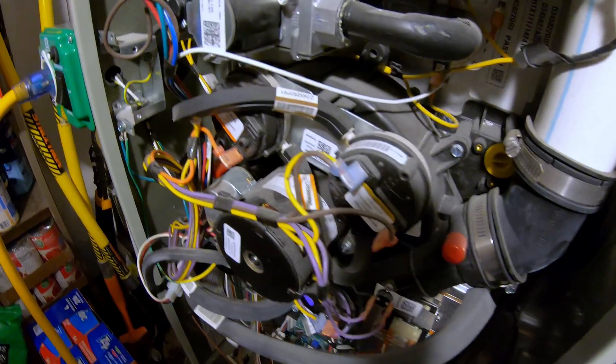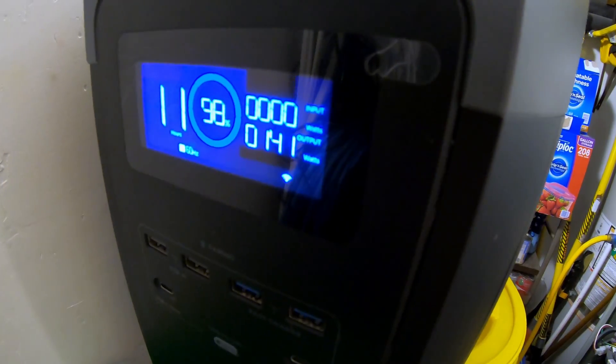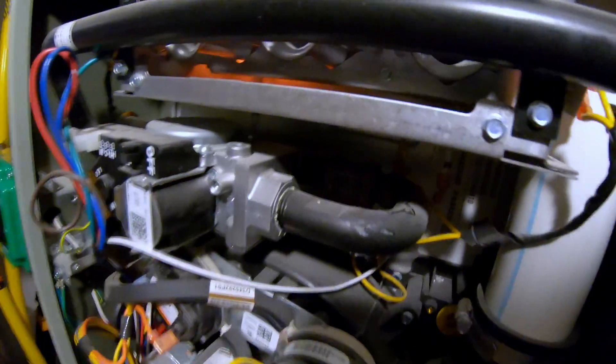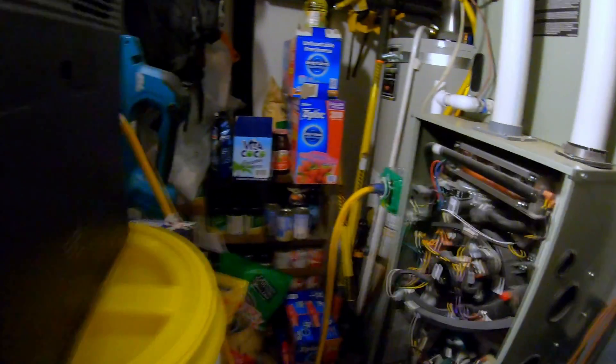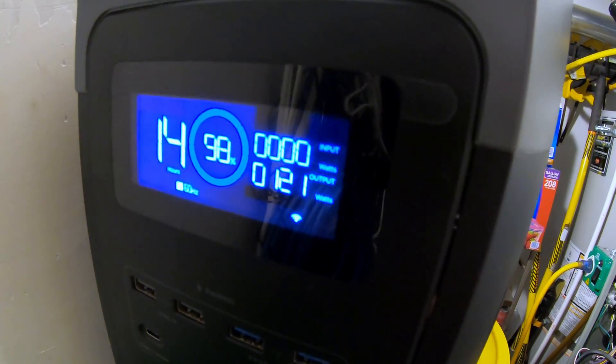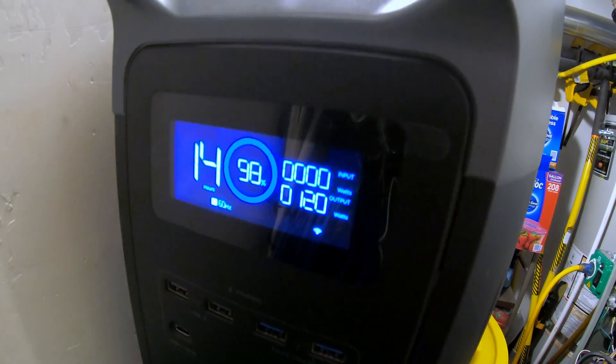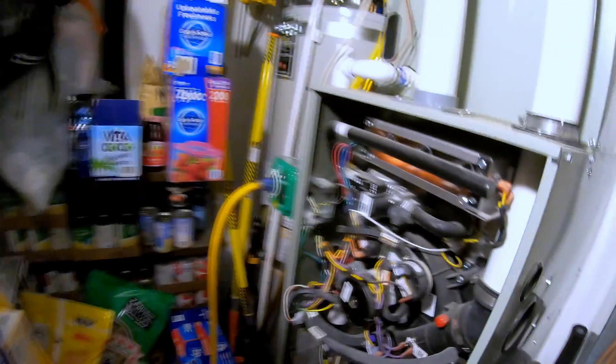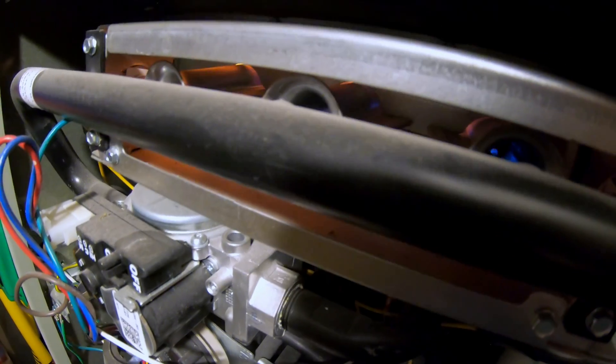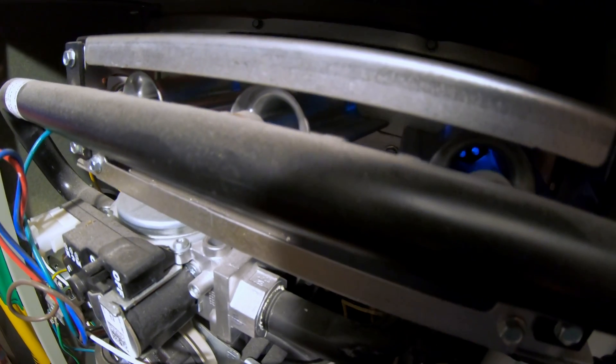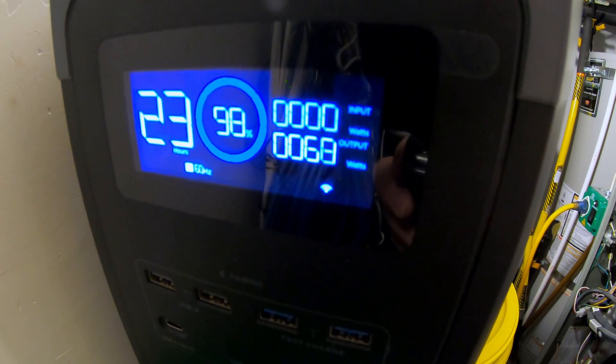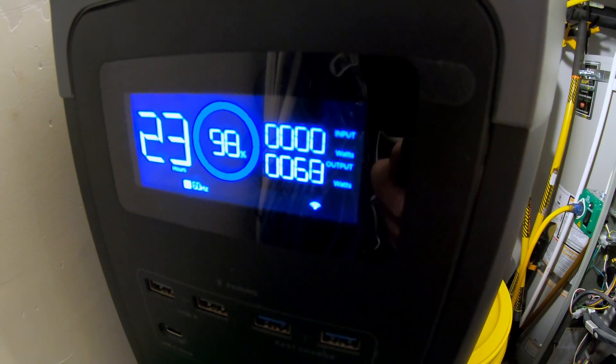Okay, the induced draft is starting. It's pulling. I missed it because now the hot surface igniter is coming. It's using some electricity. You can see 120 or so watts at the moment. There goes the gas. Now you can see what the induced draft is pulling. About 68, 67 watts.